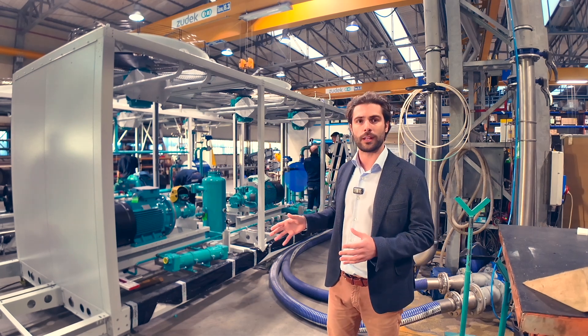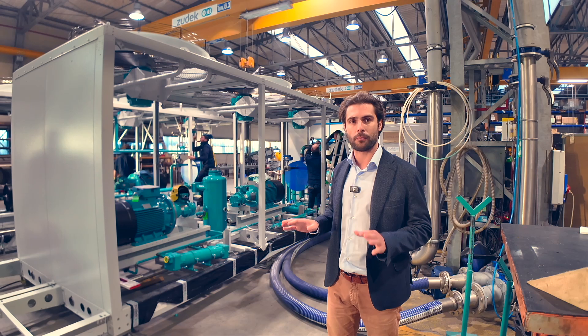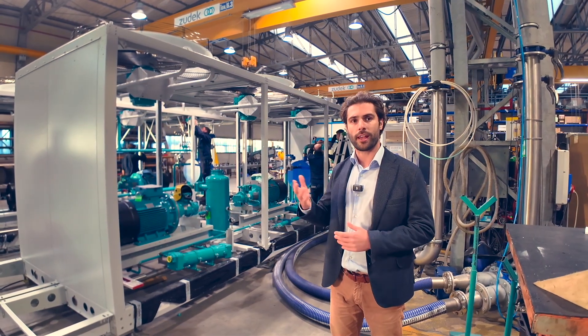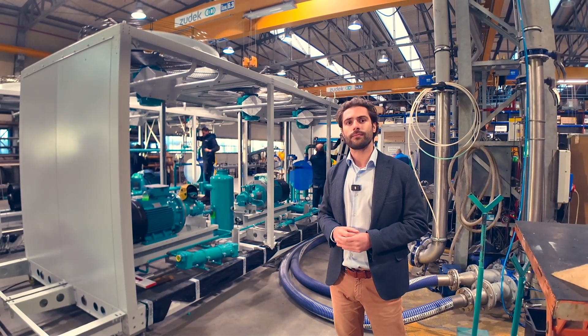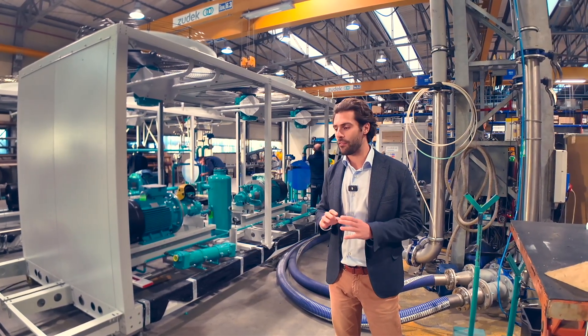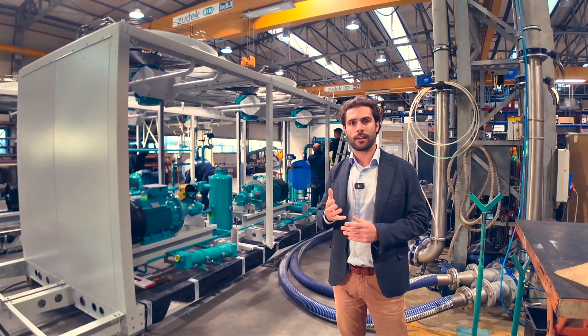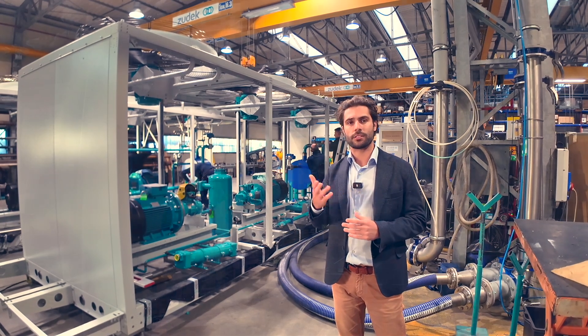This is an air-cooled ammonia unit with no water requirement, no water treatment — pure air condensation, ammonia air condensation — that can be used for HVAC and industrial applications. This is a packaged unit; everything is assembled here. The unit is plug-and-play — we ship it charged with oil and ammonia, and the startup takes just two days.